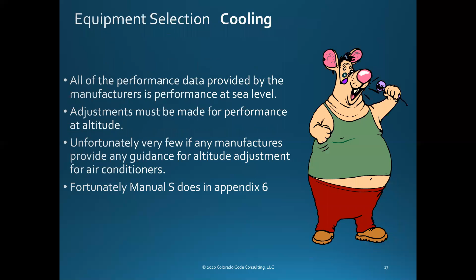So this is the air density correction factor. In our example, if at sea level in your area 800 CFM would work just fine to get the capacity, up at 5,000 feet we've got to move 962 CFM to get the same thing. If you were even higher than that, you'd have to move even more to get it to work.